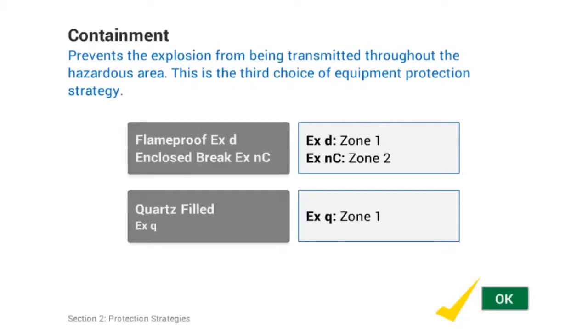The following methods allow the hazardous atmosphere to come into contact with an ignition source, but only within specially designed containers. These are manufactured in such a way as to allow an explosion to occur, but prevent it from being transmitted throughout the hazardous area. The three methods are: Flame Proof, Enclosed Break, and Quartz Filled.